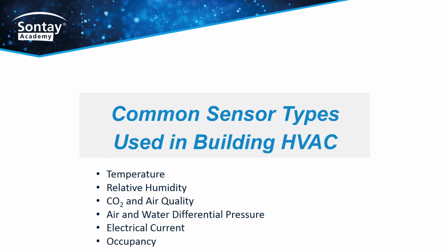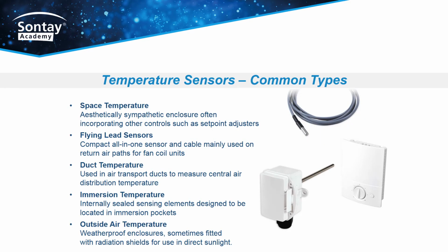Common sensor types used in building HVAC: temperature, relative humidity, CO2 and air quality, air and water differential pressure, electrical current, and occupancy. Temperature sensors. Here are some common types. A space temperature sensor: an aesthetically sympathetic enclosure, often incorporating other controls such as set point adjusters. Flying lead sensors: a compact all-in-one sensor and cable, mainly used on return air paths for fan coil units, but also seen in underfloor heating applications.